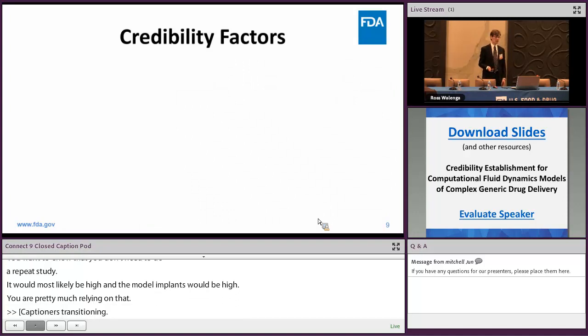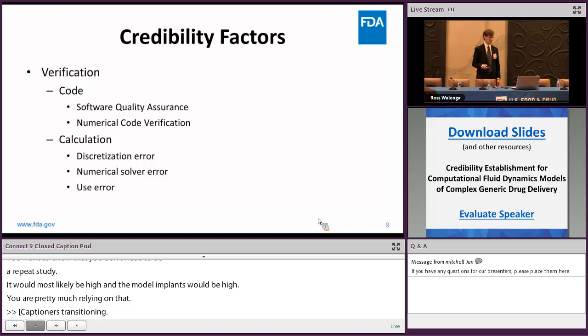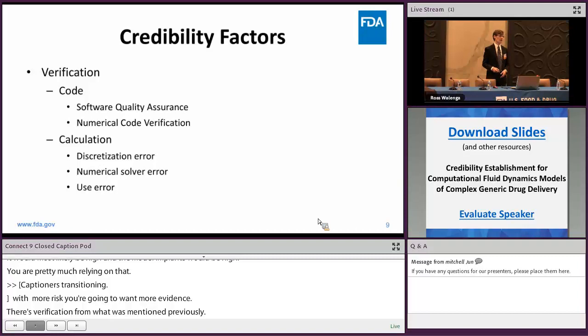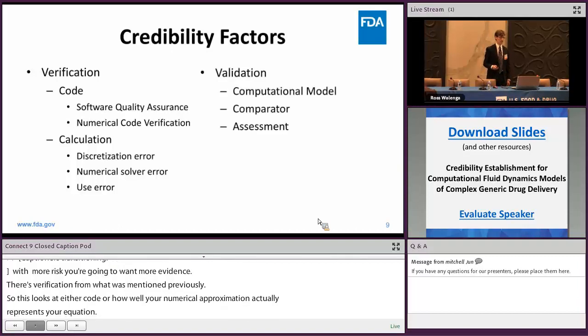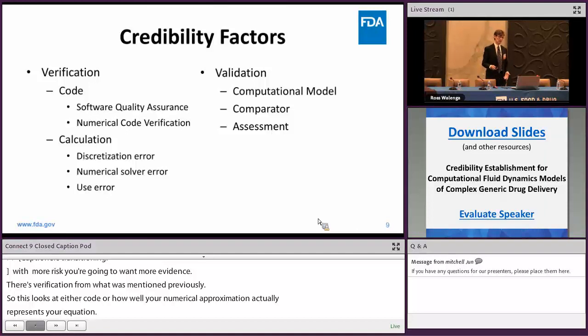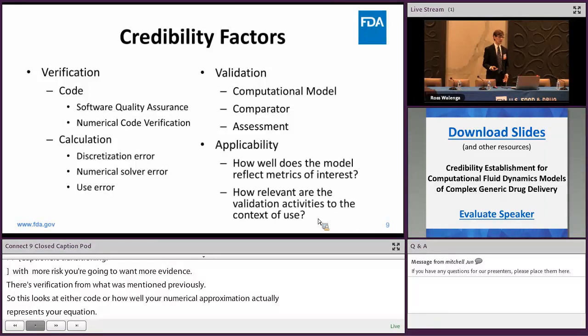Going further into how you show this model is actually useful for its intended purpose: with more risk, you'll want more evidence of credibility. There's verification — either code verification, assessing how well your numerical approximation represents your equations, or calculation verification, assessing mesh density requirements. There's also validation — comparing your model output against experimental data to assess how well it represents reality. And applicability — does your model actually represent what you're trying to measure, and how relevant is your validation to your model.